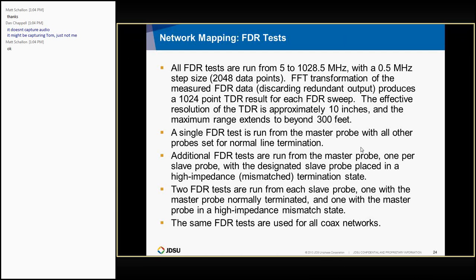A single FDR test is run from the master probe with all of the probes set for normal line termination. That's basically a reference, like the normal downstream trace. There's also, I should mention one other thing. We do take a reference sweep where you have the 75 ohm terminator connected internally. That's like your ground floor sweep. So anything that you get when you connect it to the actual cable network, you have to adjust for the ground floor sweep to account for any internal variations in the hardware itself.